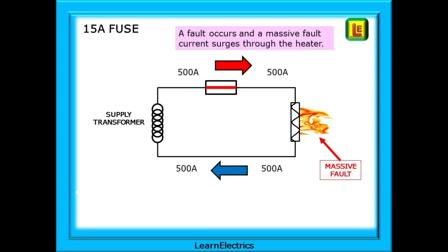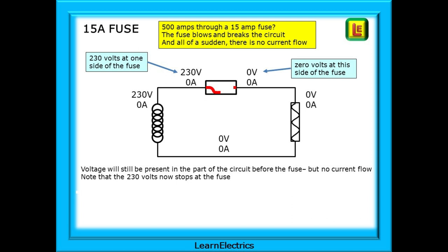Let's say a fault occurs and a massive fault current surges through the water heater. Our 15 amp water heater is suddenly drawing 500 amps or more. What happens to the circuit? How does the protective device protect things? For tiny fractions of a second, 500 amps flows through the circuit. But 500 amps through a 15 amp fuse — it just isn't going to work. The fuse blows in thousandths of a second and breaks the circuit, and all of a sudden there's no current flow. The fusible link inside the fuse has melted and now there's a gap, a break in the circuit that prevents current flow. A 500 amp fault current through a 15 amp fuse is going to blow almost instantly, protecting people, animals and property.